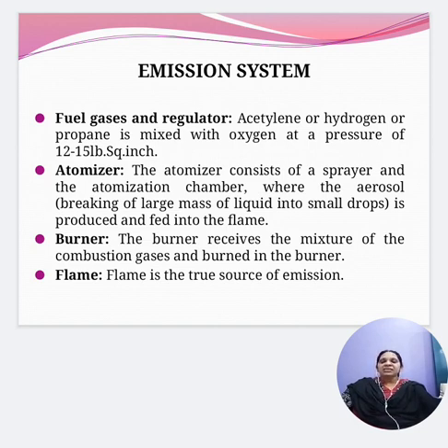Then we have the atomizer. The atomizer consists of a sprayer and an atomization chamber, where the aerosol is produced and fed into the flame. Breaking a large mass of liquid into small droplets is called an aerosol. The main heart of your flame photometer is the atomizer.